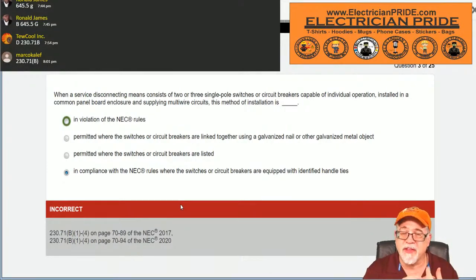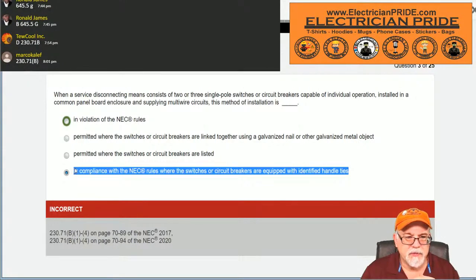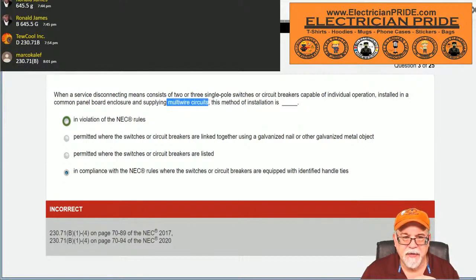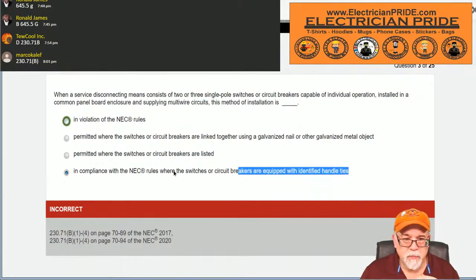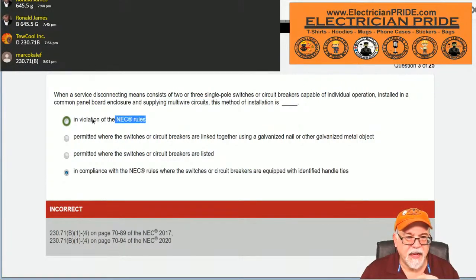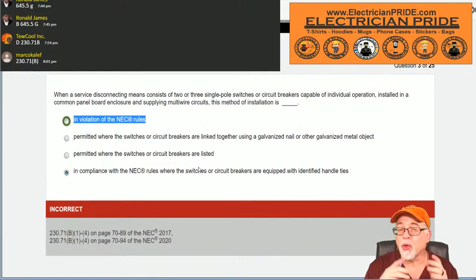This has to do a lot with the change that took place in the 2020 code. Now remember, the reason that I did it this way was because this is very much applicable to these circuits, right? Very much applicable. The reason that this is the answer, it's a violation, is because of the change that took place in 230.71b. So y'all were right on the location, but the reason we want to let this play out is because it's okay for a multi-wire branch circuit with an identified handle tie, but not for the service.